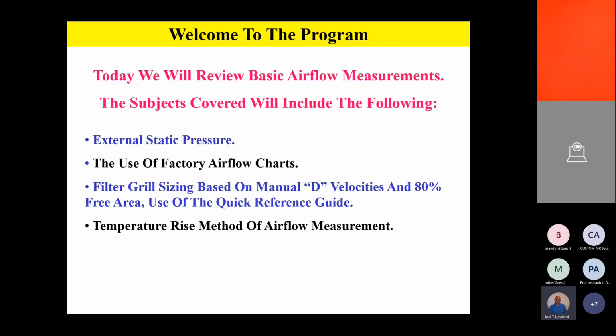So we're going to be doing some basic things today. As we review our basic airflow measurement program, the subject we're going to be talking about specifically is external static pressure, what it is, and the use of those factory airflow charts. Every one of our air handling or air moving pieces of equipment, it doesn't matter if it's a furnace, an air handler, commercial or residential, that you get from our Winsupply folks and from our Champion manufacturing Johnson Controls is going to have an airflow chart. And all those airflow charts are going to be based on external static pressure. So we're going to talk about external static pressure as a main method of measuring airflow this morning.